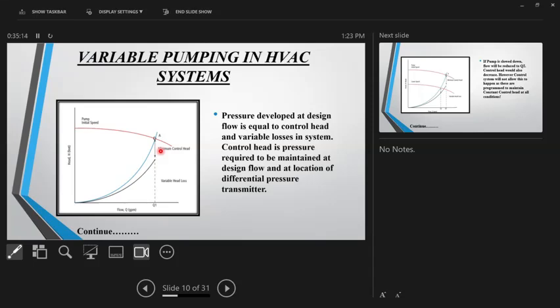Now that differential pressure transmitter setting, or set point, is obviously in terms of pressure. It could be 1 bar, 2 bar, depending upon the circuit and the loads. That DPT setting is also a pressure value. That is basically control head, or constant head. Why do we call it constant? Whatever may be the speed of the pump, whatever may be the flow, you always want to maintain that delta P constant. You modulate the speed of the pump to maintain that value. In other words, that value is independent of the flow and independent of the speed of the pump. So it is constant throughout. That's the reason why we call it control head, or DPT setting.